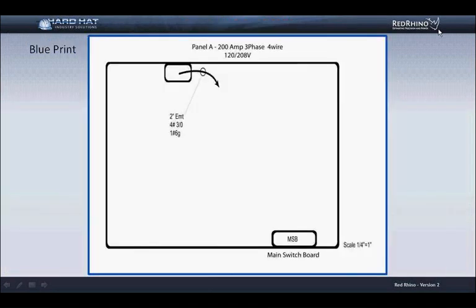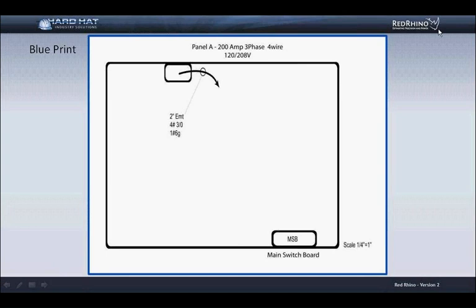Let's take a look at the drawing. The drawing shows a top view of a building containing electrical panels. It also shows a feeder conduit which runs from the main switchboard MSB to panel A, the 200 amp panel. The conduit is a 2 inch EMT with four 3-0 copper conductors and one number 6 ground. I'll demonstrate how to take off the 2 inch feeder conduit and transfer this information to Red Rhino.